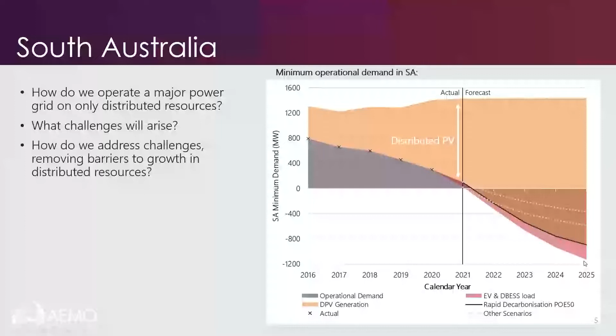I'll talk through the first 3 of these, and won't touch too much on the last one today. These are around the unintended disconnection of distributed PV during disturbances, making sure we've got sufficient load to operate the necessary units to deliver essential services to the grid, managing our under-frequency load shedding to make sure that backup system works properly, and being able to perform a system restart in the event of a system black event. Distributed PV intersects across all of these - they're all different but related issues, each requiring different approaches to handle them.